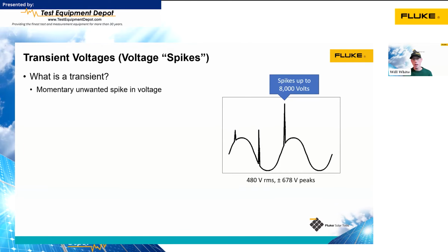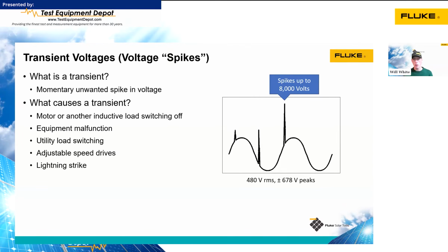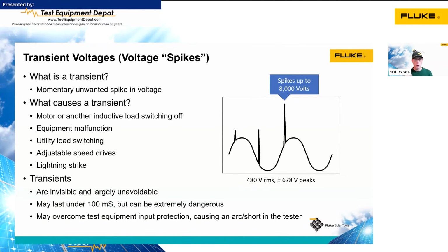Transient voltage is a momentary unwanted spike of voltage. They can be very quick, they can be very high. Usually they're coming from the utility. It could be caused by many different things. It could be from motors in a building if you're in a commercial setting. Could be from an equipment malfunction, load switching from the utility. Lightning strikes are a big one on the DC side. They're mostly invisible. You can't see them with a regular multimeter. You can see them with the higher-end power quality meters. They're very short, very fast, but they can be dangerous.